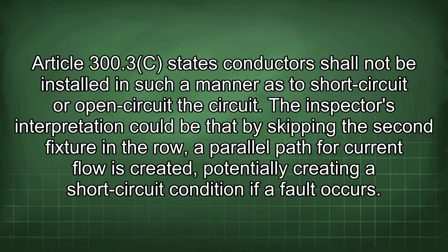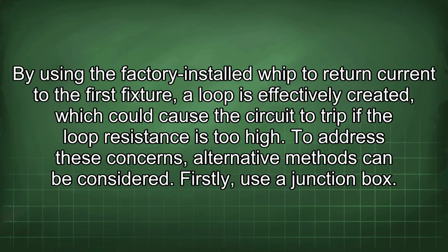Article 300.3c states conductors shall not be installed in such a manner as to short-circuit or open-circuit the circuit. The inspector's interpretation could be that by skipping the second fixture in the row, a parallel path for current flow is created, potentially creating a short-circuit condition if a fault occurs. By using the factory-installed whip to return current to the first fixture, a loop is effectively created, which could cause the circuit to trip if the loop resistance is too high.